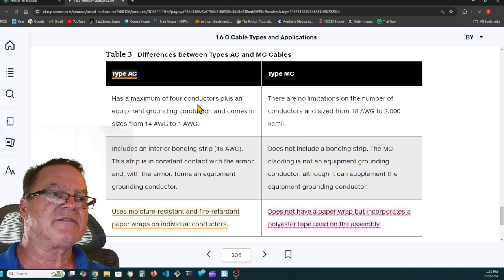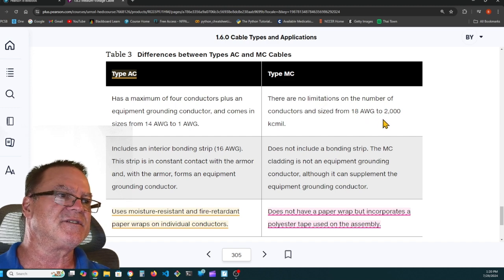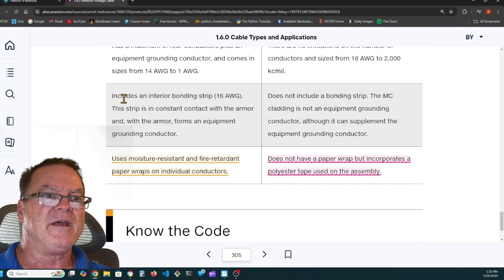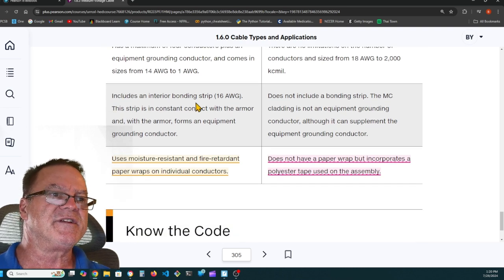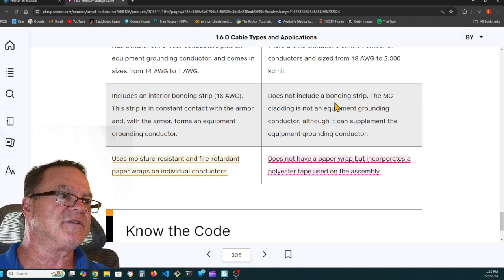Type AC has a maximum of 4 conductors plus an equipment grounding conductor. Type MC has no limitation to the number of conductors and sizes, sized from 18 gauge to 2000 kcmil. Armored cable includes an interior bonding strip. This strip is in constant contact with the armor and with the armor forms an equipment grounding conductor. Type MC cable does not include a bonding strip. MC cladding is not an equipment grounding conductor, although it can supplement the equipment grounding conductor.